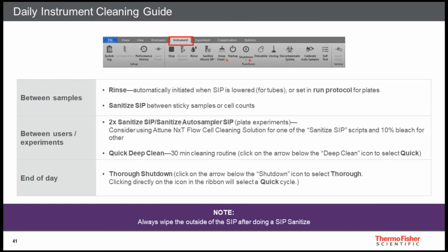As a general guideline for clog-free and issue-free operation of the system, please always rinse after acquisition of a sample. If using tube samples, please lower the tube lifter after every sample and do not let the samples sit in the lines as they may stick over time.